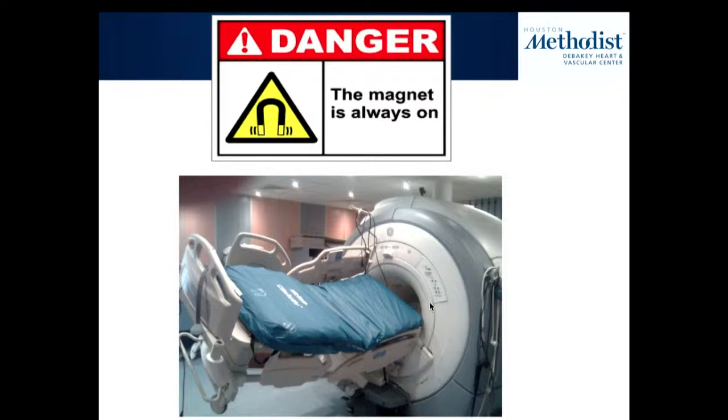So the reason I say this is important is for you guys, you get called because there's a cardiac arrest happening in the MRI suite. Well, you do not go into the room, okay? Do not go into the room. You instead ask the MRI team to bring the patient out of the room. And the reason is, what do you have? You probably have a stethoscope. Guess what? This right here becomes a projectile. It can do a lot of damage, okay?